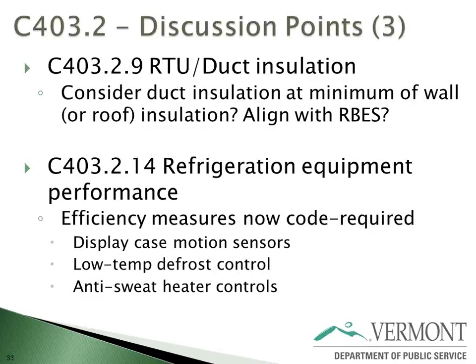That's a Vermont-specific comment. And then the duct insulation has steadily ramped up a little bit for ducts in unconditioned space and ducts in outdoor airspace. But the stakeholder input or issues that need to be resolved are: why not make it consistent with residential? So the residential requirement has essentially, through some clever language, said you either insulate your outside ducts to the nearest wall surface, which in a house would typically be your roof. So if your roof's R49, I'm going to say, make the ducts R49. Well, it makes more sense just to bring the ducts inside, wherever possible. Bring them in. That's the goal. Bring them in, rather than just say that. They sort of give you an option.